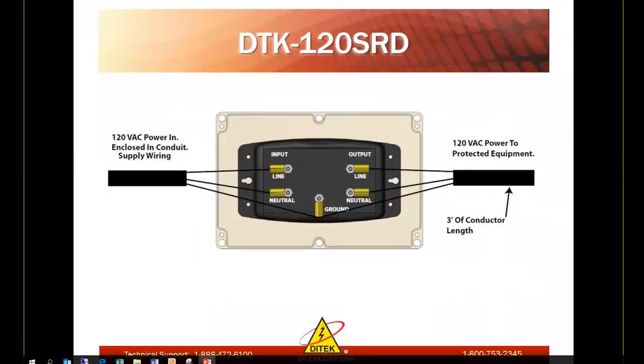On the 120SRD, this is a diagram of how the device is wired in series. It's a 120-volt power feed from that supply circuit into the device: hot, neutral, and ground. Then we continue through the device with hot, neutral, and ground to the fire panel. Again, remember, to that fire panel you need that 3-foot loop of conductor length. It's not linear, it is wire distance.